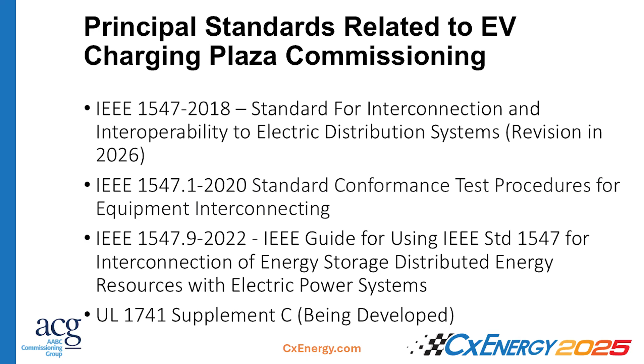1547.1 is the test procedure for conformance to that standard, and it correlates very closely with UL 1741 for the inverter requirements. Then 1547.9, published a couple of years ago, gets more detail on interconnection with energy storage systems.